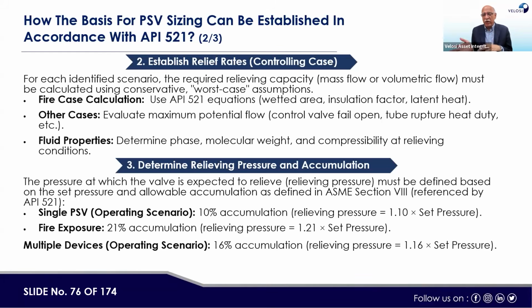In case there's a fire outside, how much fluid would be there? What is the wetted surface area? Then accordingly, we have to calculate the volume of the fluid which will be going out. In this scenario, we need to determine what the fluid is, whether liquid or gas, what the molecular weight is, what the effect of the heat on this particular fluid is, and then accordingly whether there will be a single PSV or double PSV, what kind of exposure time, and what kind of overpressure we need to consider.